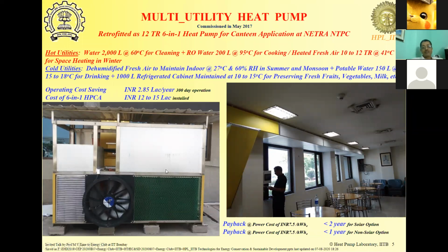And the beauty of this is that the utilities need not be consumed at the same time. So if cooling is required now and hot water is required at a later time, we don't have to have a separate storage space. The storage spaces were built within the heat pump itself. Now, this was a 12-ton compressor-based heat pump, which was deployed at the National Thermal Power Corporation R&D headquarters at Greater Noida. This has been operating there since May 2017.